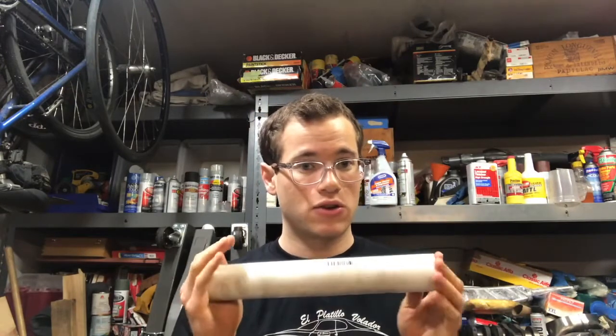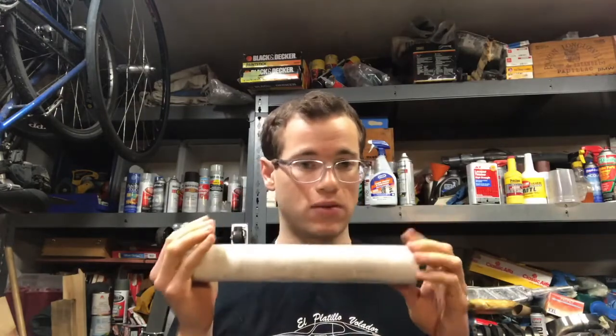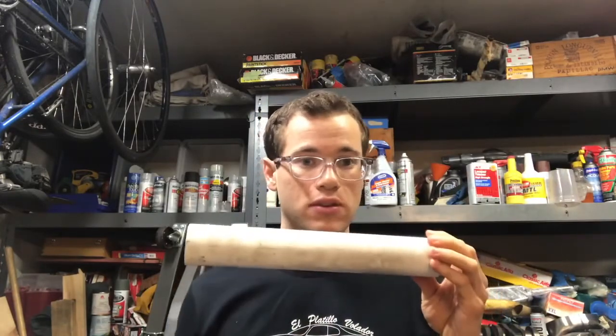One issue with contactless flow sensors is that temperature perturbations or temperature gradients inside the pipe, as well as the actual media, make a big difference in how quickly the ultrasonic pulse moves through the pipe and the fluid inside it.